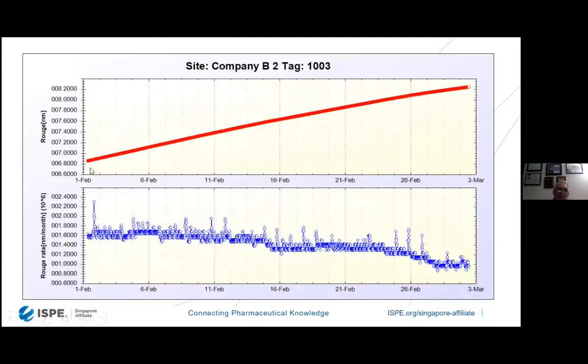This is a rouge system over here. Notice we're running between 6.8 nanometers up to 8.2 nanometers over time. And if you look at that, a one month time period doesn't increase more than 1.4 nanometers. But if you look at the blue line underneath it, it's running between 1.6 or 1.5 nanometers and up to as high as 2. And you can see there are these little peaks and they go up and down.